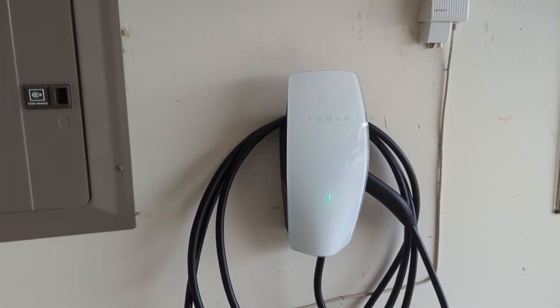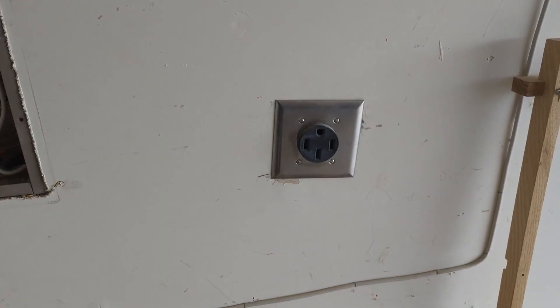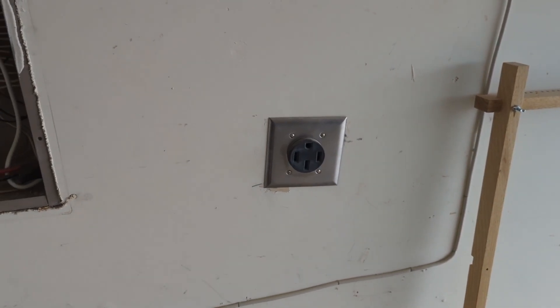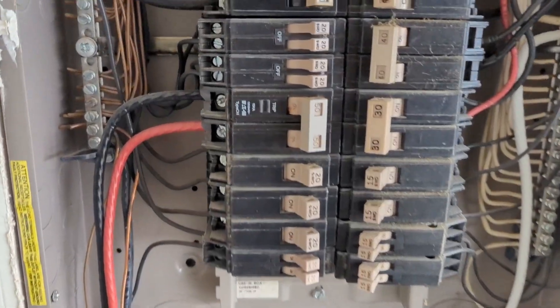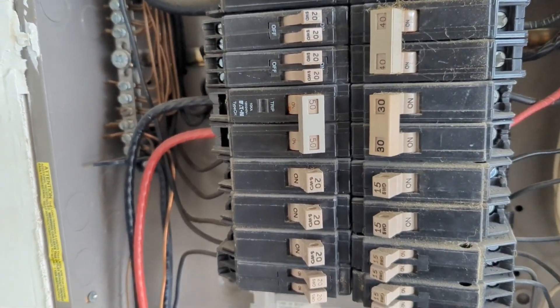Hi! In this video I'm gonna show you how to install a Tesla wall connector. Despite that we have two 240V outlets already installed, we're gonna have to replace it, and we're gonna have to replace our breaker because the new charger will require a 60A breaker.